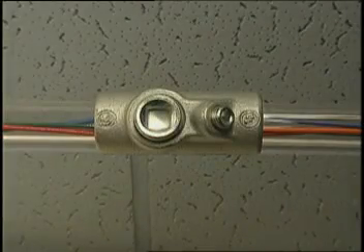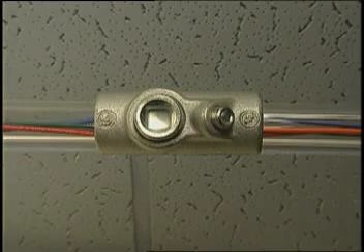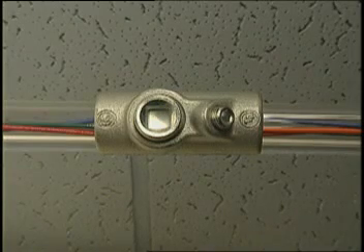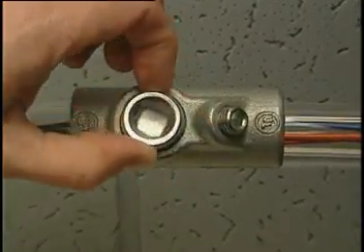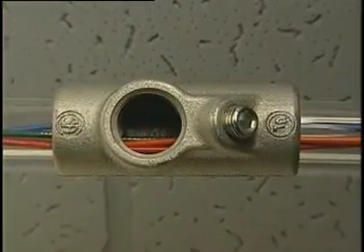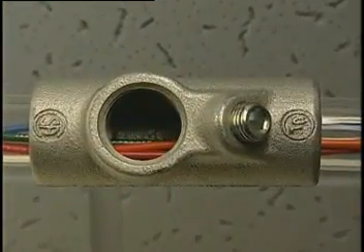For illustration purposes only, we're using clear conduit to demonstrate the Chico Speed Seal. First, prepare the sealing fittings by removing the plugs. The Chico Speed Seal compound will start to gel in four to five minutes, so it's important to prepare your seals before mixing the material.